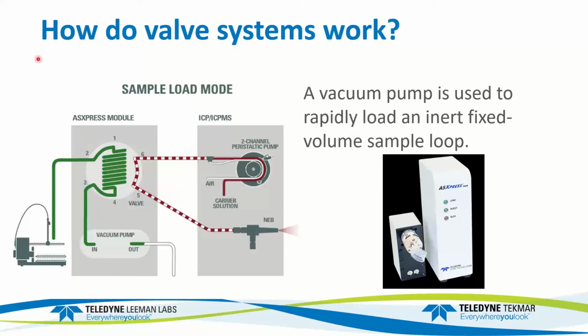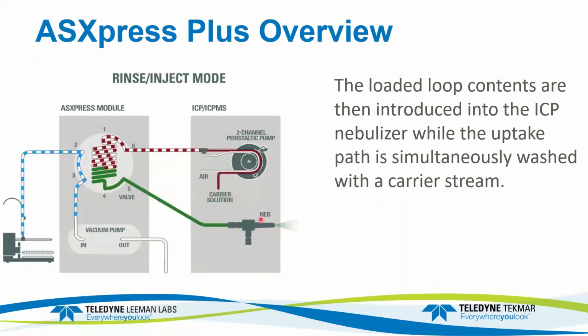Then once the loop has been loaded, the valve switches, and now the peristaltic pump with the carrier solution pushes the sample from the loop into the nebulizer to be analyzed. And if you notice, with this setup, the sample never touches the pump tubing. And pump tubing is always one source of carryover because some elements stick to pump tubing more than others do. So it's a really nice feature to be able to eliminate that. And filling up the loop is very fast. Just a couple of seconds, and we'll see that in a second.